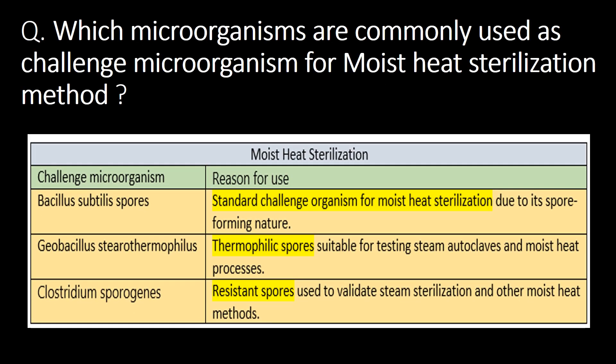Which microorganisms are commonly used as challenge microorganisms for moist heat sterilization? Moist heat sterilization is used in autoclaves or high-pressure steam sterilizers. This method is commonly used for closed chamber sterilization, such as manufacturing tanks and lyophilizer chambers. Refer to the table below for challenge microorganisms and the reason for their use.